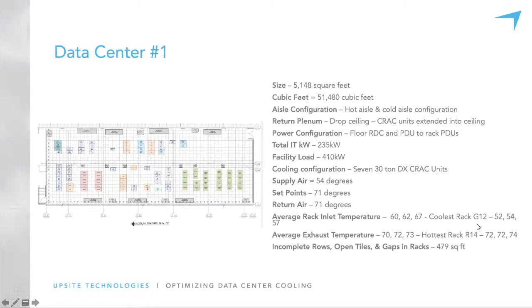I did throw some other information down here. Average rack inlet temperatures, 60, 62, and 67. If we look at the ASHRAE recommended range, that's 60 degrees. That's 1 degree above the bottom of that range. And I've never seen this, but I think about this all the time. If I have some pretty hot pieces of equipment, exhausting air in the 80 to 90 degree range, and I'm putting air in at 59, my worry at that bottom range, and I've not seen this happen, would be the formation of condensation just based on the extreme cool air and the extreme hot air. And again, I've not seen that happen, but when I see a temperature at that bottom range, that's the concern that I have.